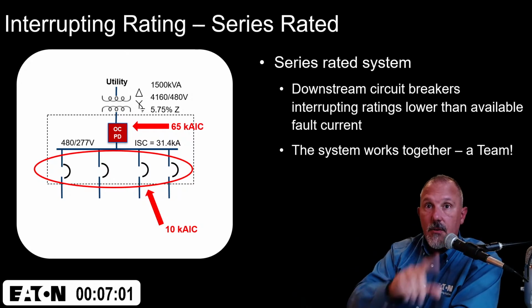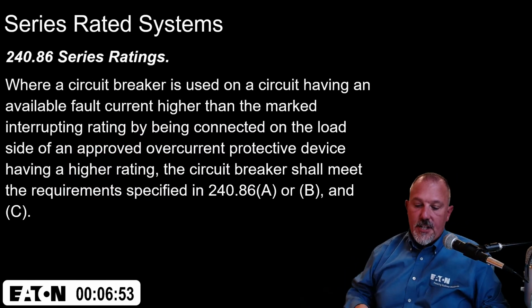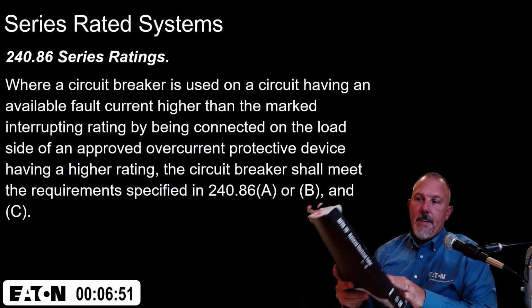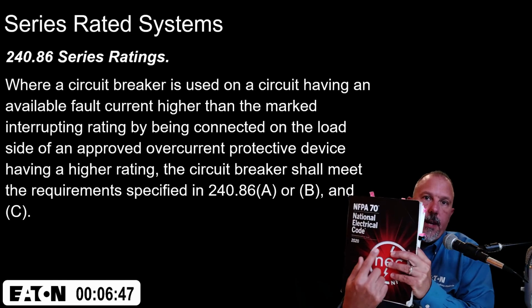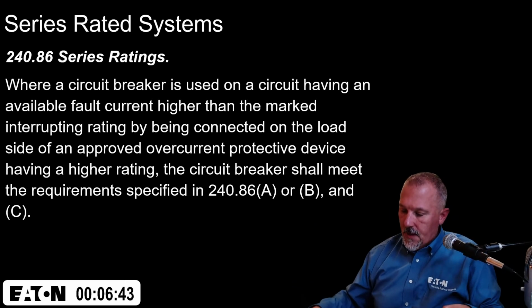So they work together as a team, whether it be a fuse upstream or a circuit breaker and a circuit breaker downstream. Now, 240.86 is the section, and I am using the 2020 version of the National Electrical Code.